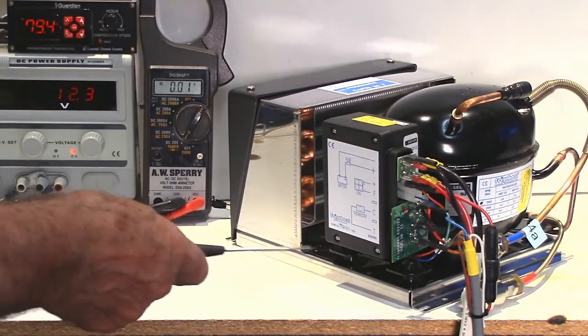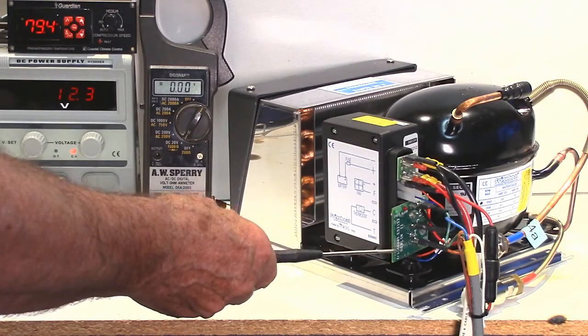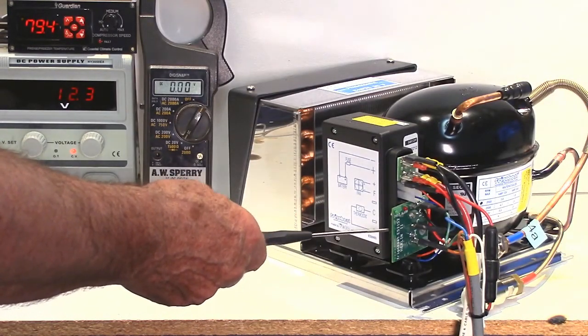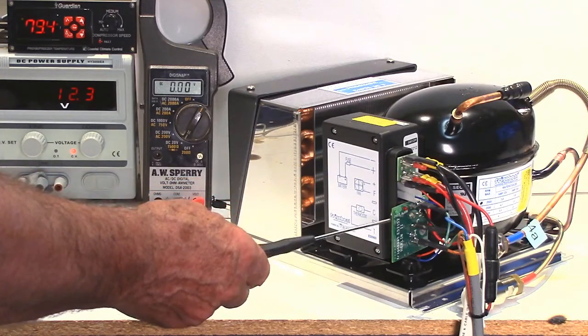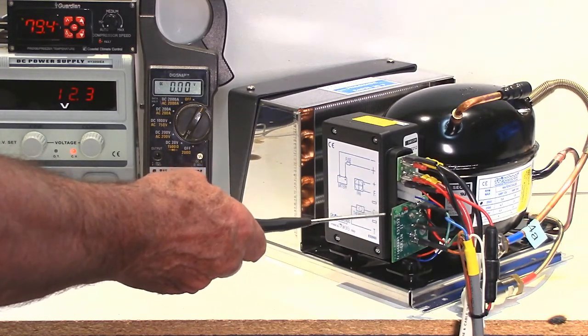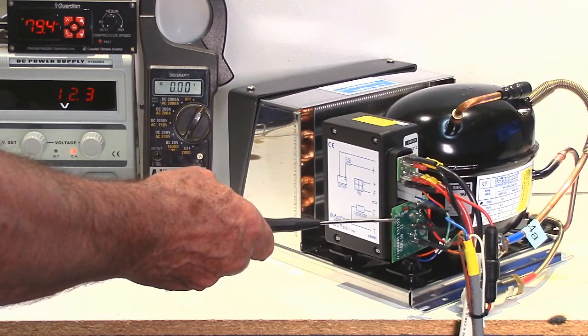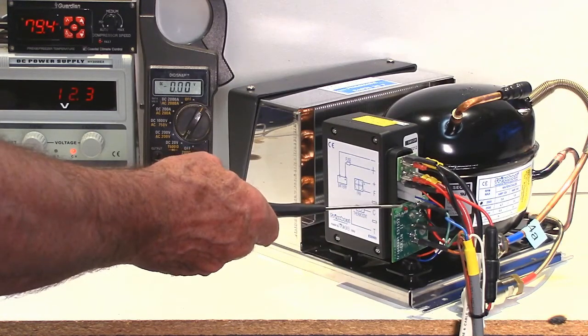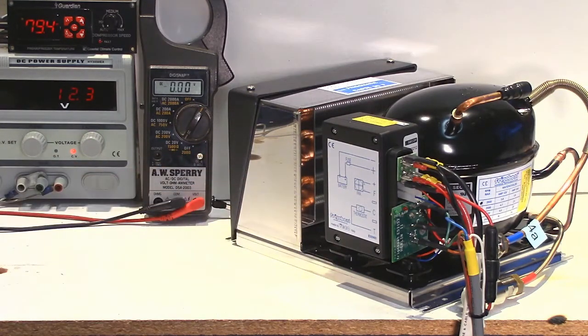So now we have the Merlin 2 Compressor Speed Controller plugged in, in place of the speed board we had before. And you can see it has two LEDs on the top. One is for the compressor speed, the green LED, and the red one is the fault LED. Both of them flashing once which means that the compressor speed should be on the lowest speed, one out of six. And the red flashing we know is because there is a problem with the voltage somewhere.